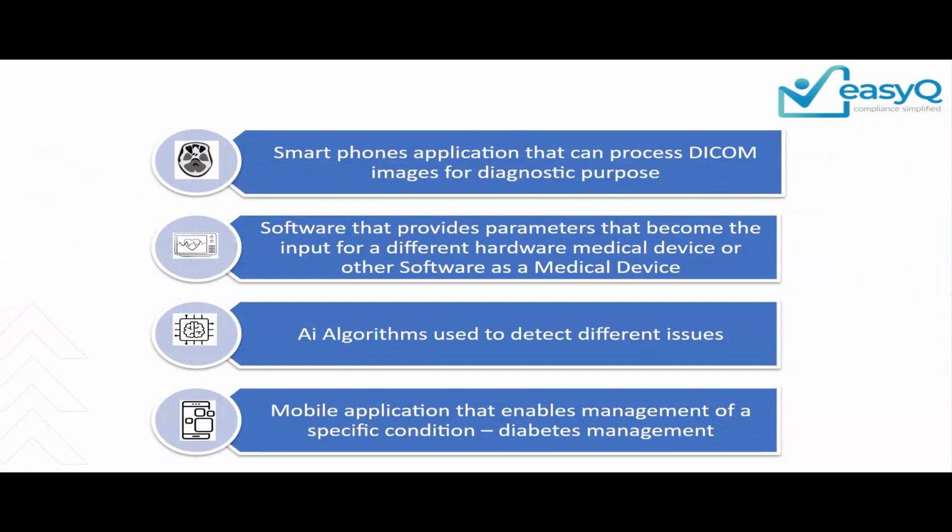Even software which helps you process data or some information and gives you the output, which you use to define, let's say, the dose levels of an X-ray or a CT or MRI system. The software which does the analysis or the calculation and gives you the output can also be seen as a software as a medical device. Keep in mind here that the software is not controlling the system. It is not software in a medical device. It's completely separate software. You feed some information to the software.